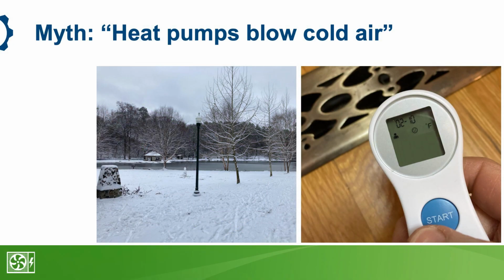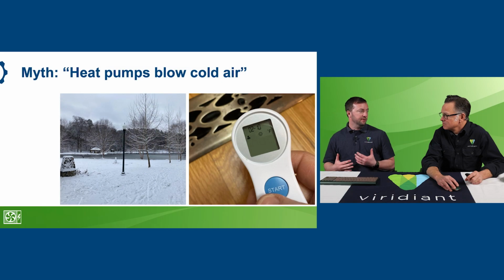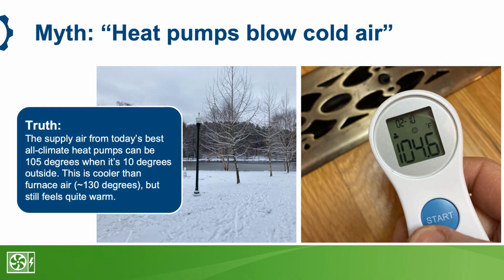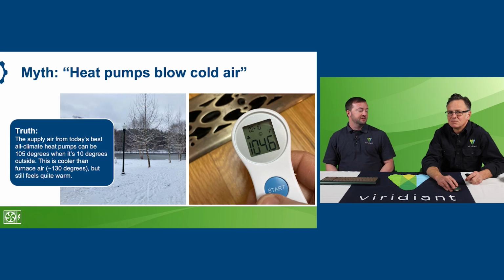Many folks are familiar with furnaces or old boiler systems, and they may be expecting a heat pump to have those same hot temperatures that you get from those fossil-fueled systems. And in fact, those systems do have a hotter temperature. Furnaces often put out air at the supplies around 130 degrees. The temperature out of a supply from a heat pump is going to be lower, but still quite warm. It'll be around 100 degrees. So that may lead them to believe that because it's a lower air temperature, it's not going to keep their home warm. It's important to let them know that that cooler air temperature is a normal operating condition, and it's something that they should expect, but it will still keep their house warm.